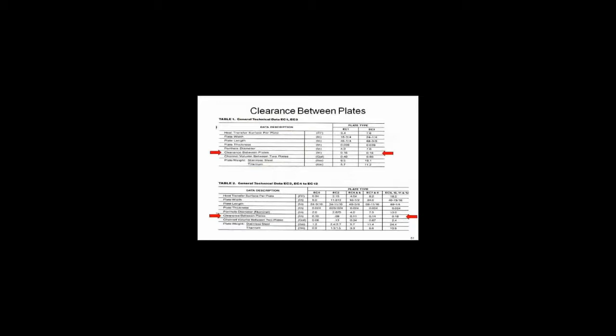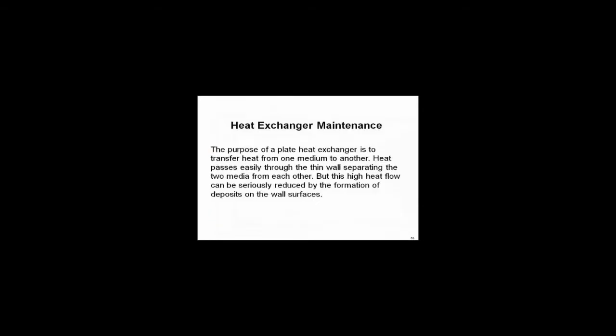We want to look a little bit real quickly at fouling, and it's a subject that people don't talk about enough because, very simple, you're dealing with cooling tower water. And in the air, you've got all kinds of stuff. Why is this important? It's a typical clearance mark with a little red area here of a typical plate. As you can see, it's pretty tight, 0.16 inches on a typical plate heat exchanger. So for all practical purposes, and this is an I&M from plate manufacturers. We went through and looked at a whole bunch of them, and all of them have the same information identical in I&M. It says, very simple, we've got thin wall heat exchangers, high heat flows, but it can be seriously reduced if we get deposits. And we're still telling you, you've got to do maintenance. If you're going to do maintenance, it's fine, but you need to have a pretty clean system. You need to do maintenance on the heat exchangers to make sure we don't foul them up. That's just what the I&M is saying, and we find, unfortunately, a lot of heat exchangers on water-side economizers that the maintenance people have just simply turned off and bypassed because they're fouled and they don't want to do the maintenance.